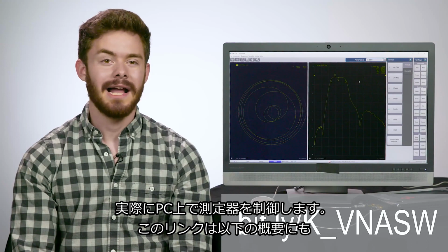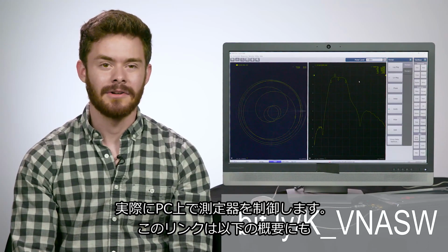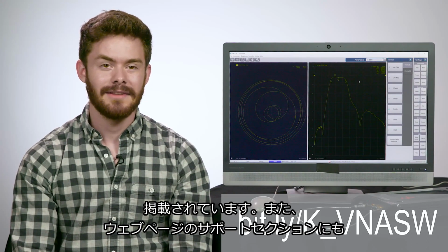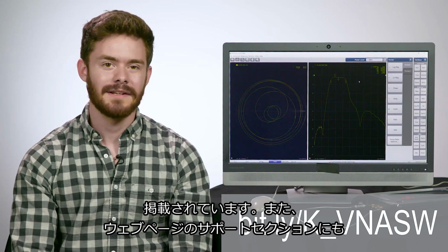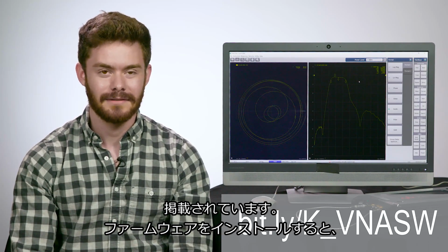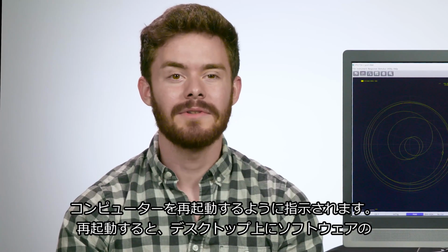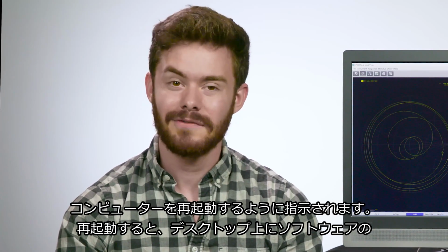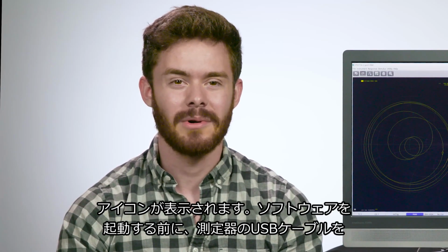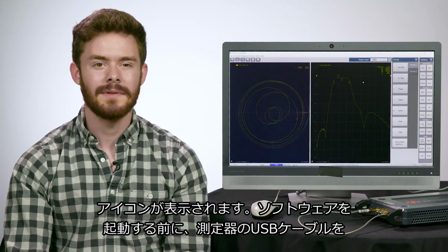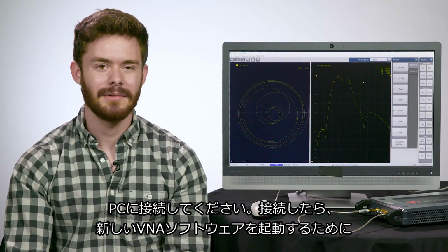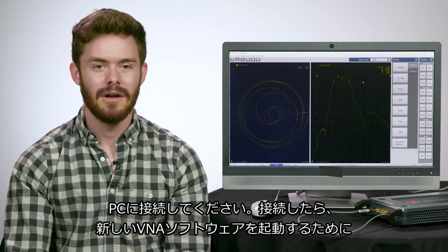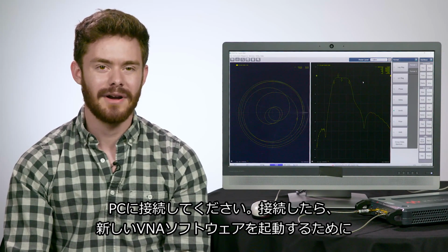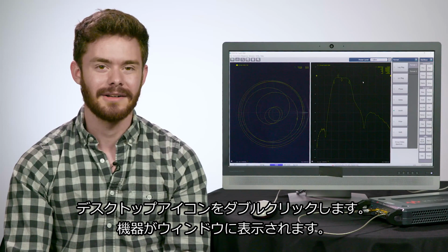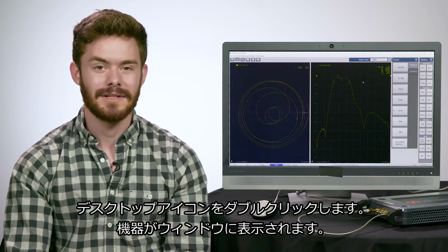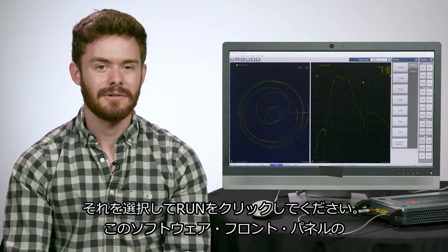The firmware is what will actually allow you to control the instrument on your PC. You can find this link in the description below as well, or you can find it under the support section of the web page. Once the firmware is installed, it will prompt you to restart your computer. After the restart, you'll see an icon for the software on your desktop. Before you open the software, plug in the USB cable of the instrument into your PC. Once you do this, open the new VNA software by double-clicking the desktop icon. Your device will show up in that window. Select it and click Run.